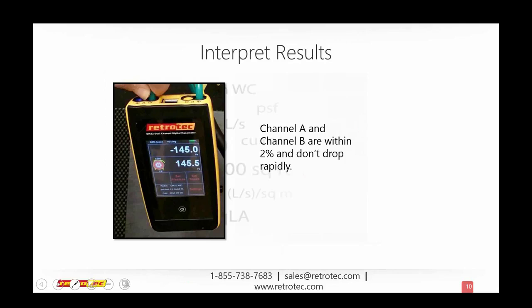You move that around until you get the baseline pressure in the building, across the building, moving as little as possible. And then you take that tube, which will normally be a red tube if you're inside the building, and that red tube is common to each channel of your gauge. So we're commoning the reds, or we're commoning the outdoor, but we're running separate tubes to different places in the indoor because we want to see how the indoor pressure is different. We need to measure those pressures to a common base, and that common base we establish by, again, manifolding or teeing all of the red tubes together. And then inside the building, we'll be running blue tubes at different parts of the building.